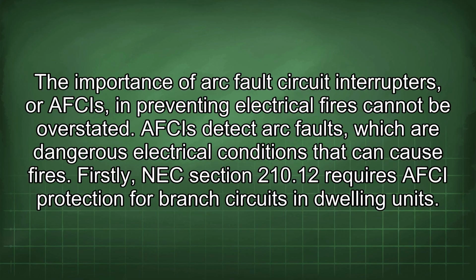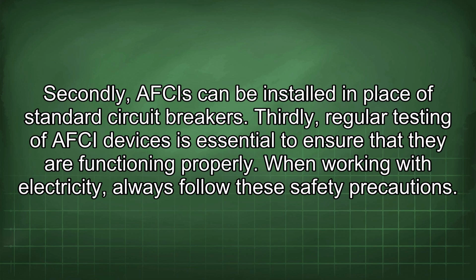The importance of arc fault circuit interrupters, or AFCIs, in preventing electrical fires cannot be overstated. An AFCI detects arc faults, which are dangerous electrical conditions that can cause fires. Firstly, NEC Section 210.12 requires AFCI protection for branch circuits in dwelling units. Secondly, AFCIs can be installed in place of standard circuit breakers. Thirdly, regular testing of AFCI devices is essential to ensure that they are functioning properly.